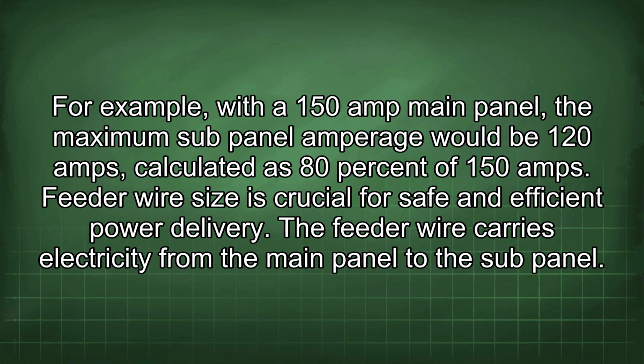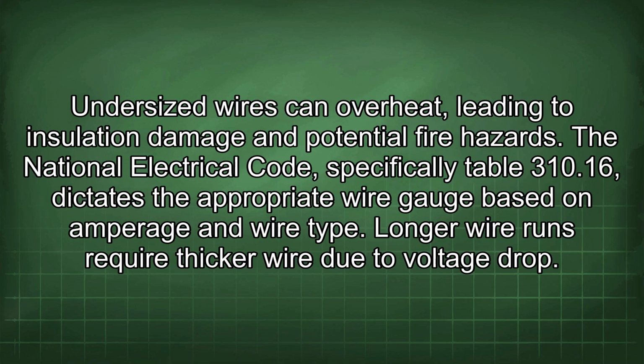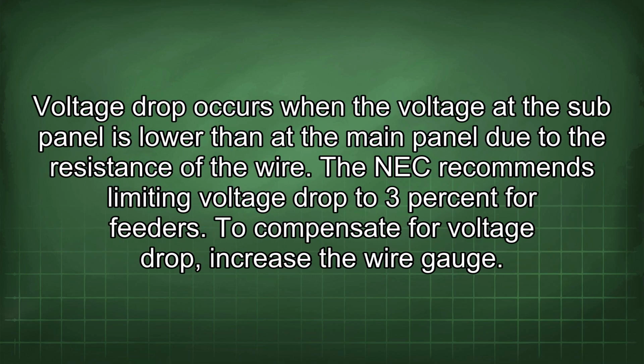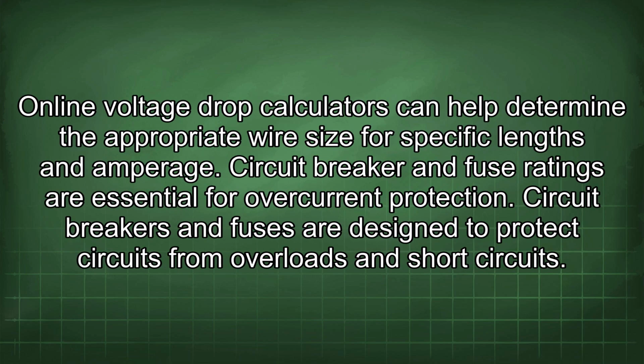150 amps. Feeder wire size is crucial for safe and efficient power delivery. The feeder wire carries electricity from the main panel to the sub-panel. Undersized wires can overheat, leading to insulation damage and potential fire hazards. The National Electrical Code, specifically Table 310.16, dictates the appropriate wire gauge based on amperage and wire type. Longer wire runs require thicker wire due to voltage drop. Voltage drop occurs when the voltage at the sub-panel is lower than at the main panel due to the resistance of the wire. The NEC recommends limiting voltage drop to 3% for feeders. To compensate for voltage drop, increase the wire gauge. Online voltage drop calculators can help determine the appropriate wire size for specific lengths and amperage.